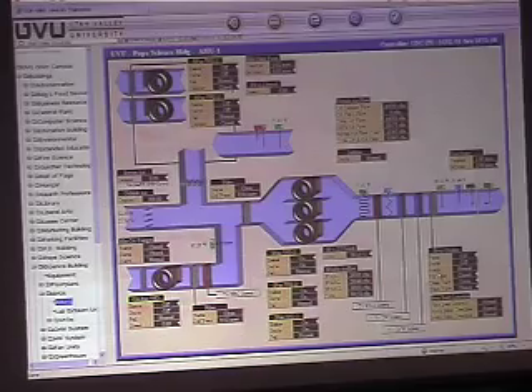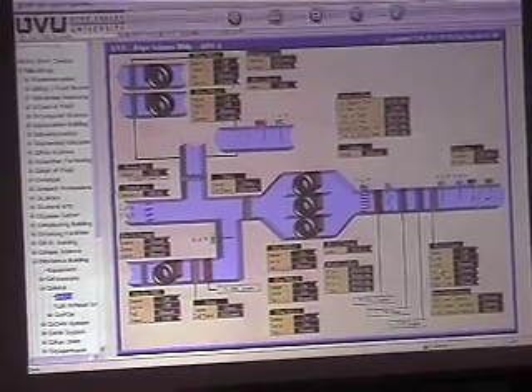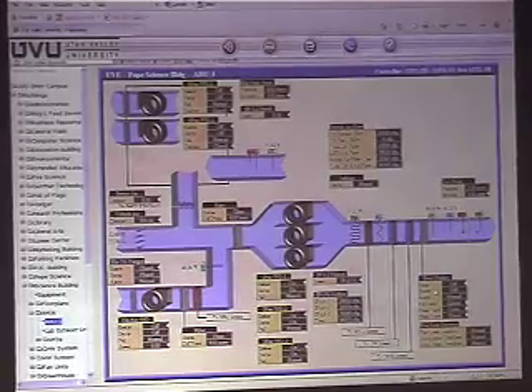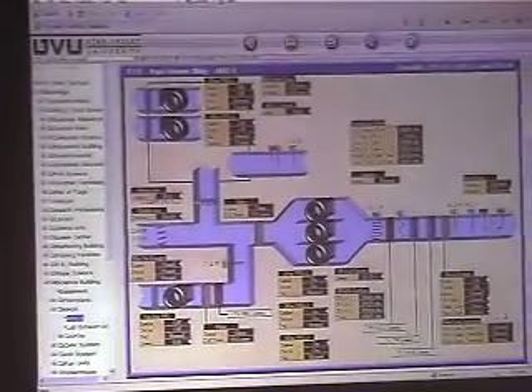So basically you've got the fill valve, which will fill up the sumps, and then you've got the pump enabled, and we're picking up a status off. All 4 pumps have to be running up there for us to show status on. That way you'll know if any of them kick out that you've got a problem up there. And then there's the fill valve, the drain valve, and the flush valve.